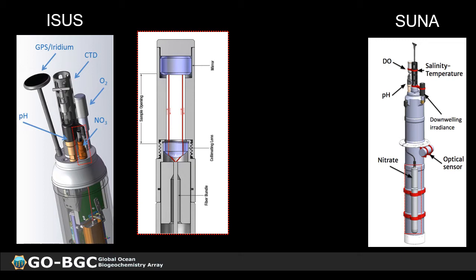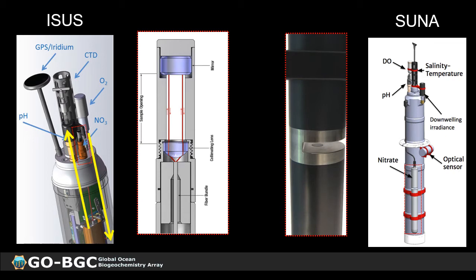Basically, you shoot light from the lamp inside of the float housing, and it goes up a fiber optic cable, and the light shoots through the seawater, bounces off a mirror, and comes back down through another set of fibers and into the spectrometer. This is how the ISUS measures absorbance in seawater. Suna, on the other hand, has the lamp and the spectrometer in different parts of the housing, and the light just goes through from one housing to the next. These are the differences in the optical setup between the two sensors. But because the critical components of the sensor are identical, the performance of the two sensors is comparable in the field, which is good news.